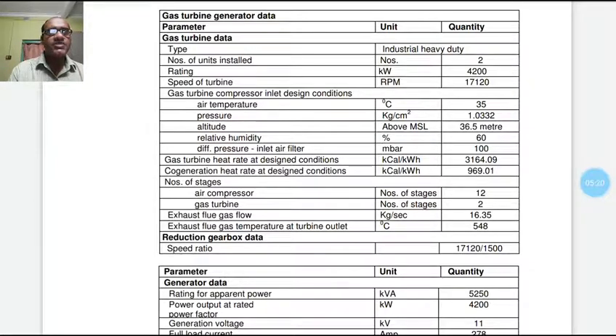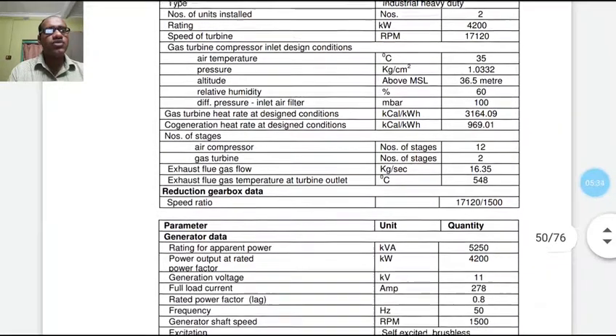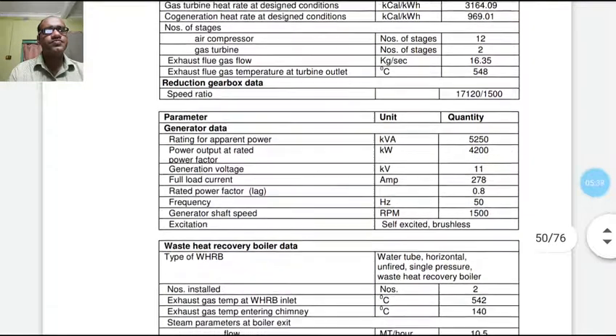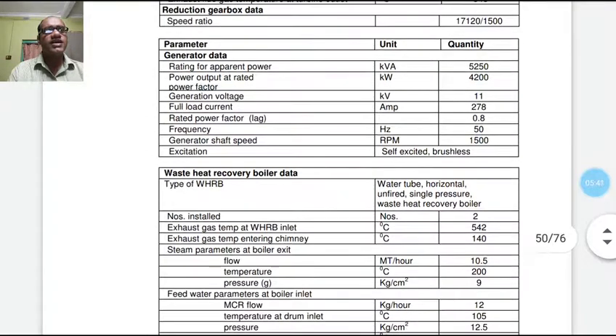Now at this high temperature, this exhaust flue gas we are utilizing in an unfired waste heat recovery boiler. Gearbox data: 17120 by 1500. Now generator data: 5250 kVA, kilowatt 4200, generation voltage 11 kV, full load current 278 ampere, rated power factor 0.8, frequency 50 Hz, generator shaft speed 1500. Excitation is self excitation brushless.